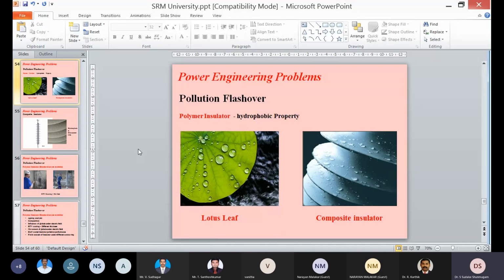Right now, another study which is happening when it comes to insulation selection, especially polymeric insulation, is how to give optimal corona ring design. That is still an area of research. Why do polymeric or composite insulators provide better pollution performance? Because of their hydrophobic property. As I told you earlier, even though the contaminant accumulates on the surface of the insulator, if it cannot be wetted by water, how can it conduct? We know that in order for current to flow, we need a continuous current path. If the water cannot wet the surface, the possibility of getting a continuous conductive path is very low, and because of that phenomenon, that is the hydrophobic property, polymeric insulators are gaining a huge market in India right now.